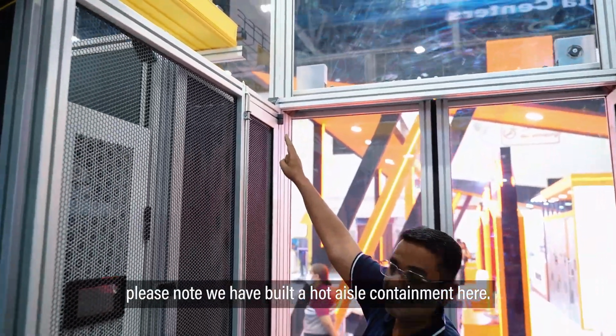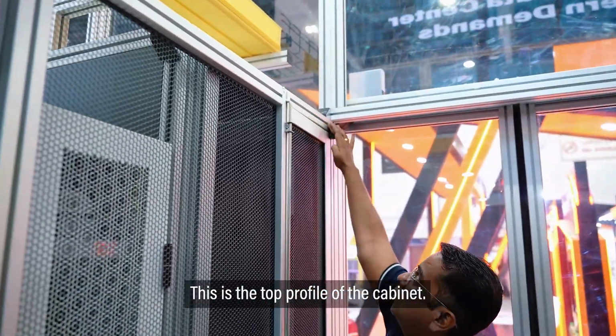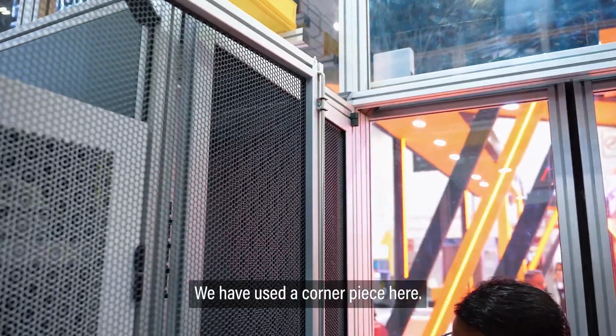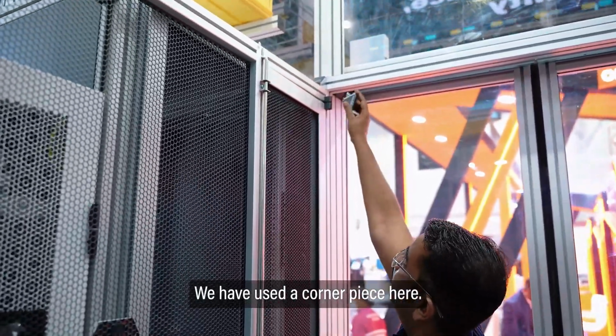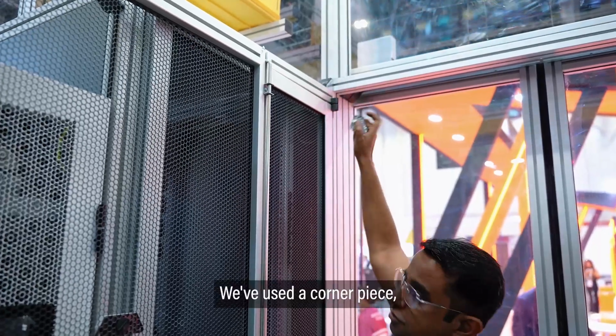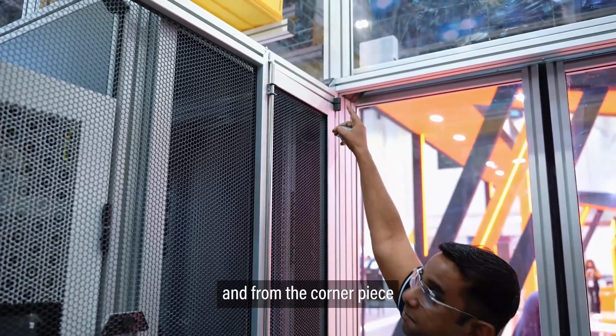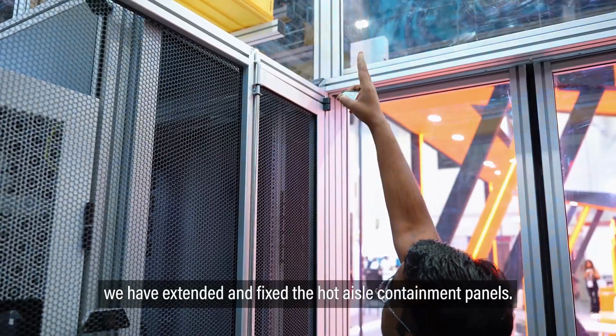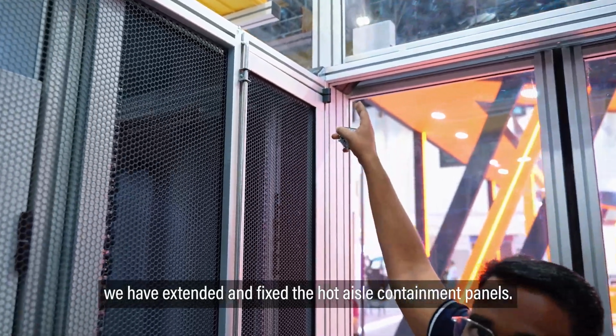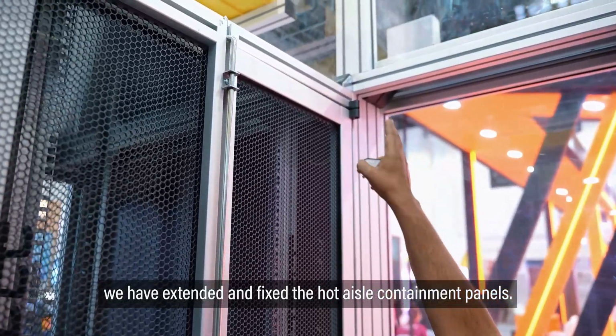In future, if you need to add a cold aisle or hot aisle containment, note that we've built a hot aisle containment here. This is the top profile of the cabinet, and we've used a corner piece here. From the corner piece we've extended and fixed the hot aisle containment panels.